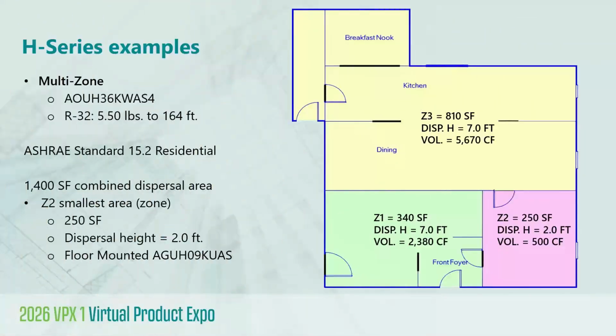So let's take a look at a scenario where you could find, say, a multi-zone system where you've got this challenge of a dispersal volume that might be too small to manage the entire system charge. Now, I'd like to preface this example by emphasizing again that the vast majority of the time, system charge compliance is achieved out of the box, as we've discussed, or with a gas sensor to activate circulation. But let's take a look at kind of a worst case scenario, you might say, to demonstrate the compliance flexibility using the LDS options that we have available.